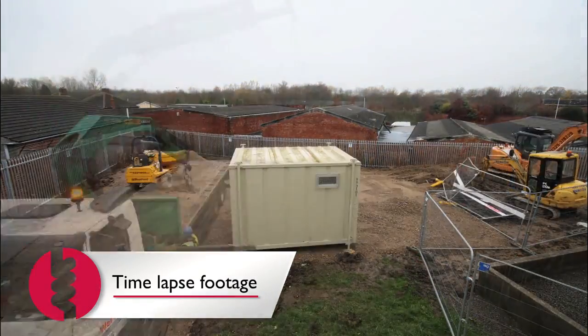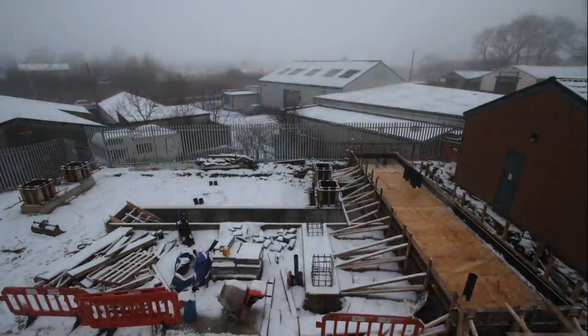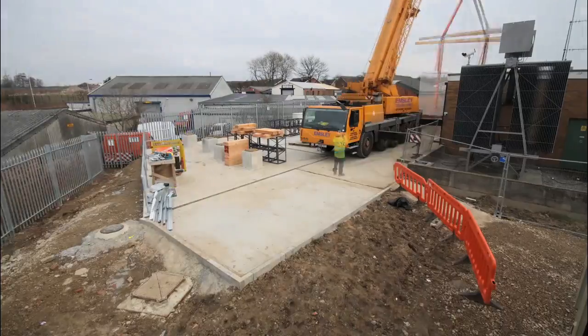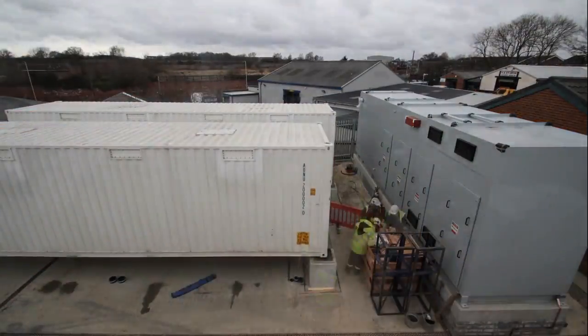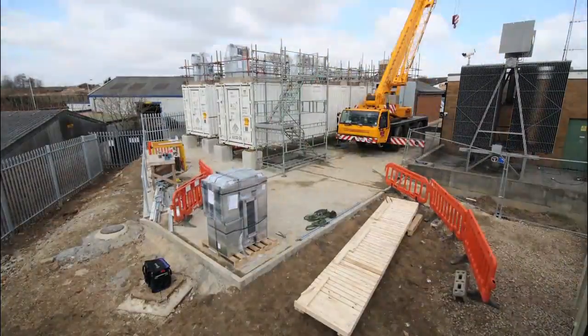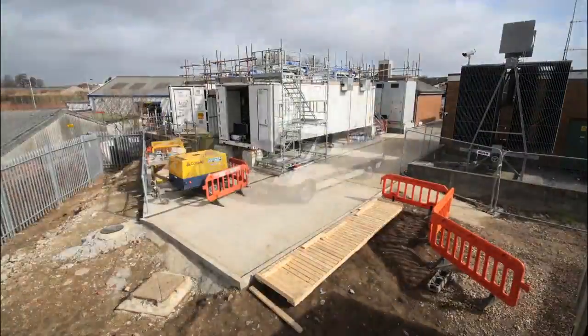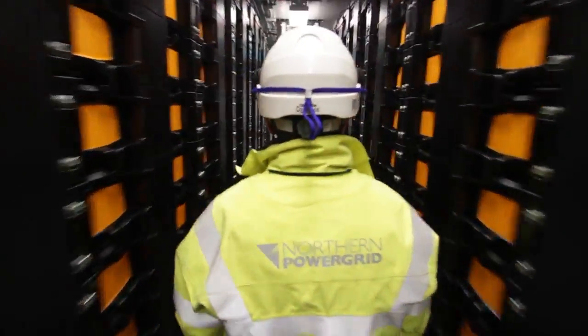Many of the sites were quite space constrained, so there are some challenges in installing them — we had to get a crane in here. These battery containers ship at about 50,000 pounds each, and when fully loaded they're actually above 100,000 pounds, so getting the equipment in here to move these around on a relatively small footprint was a bit of a challenge. Here at RISE Carr, we have the largest system of two battery containers and one central inverter.